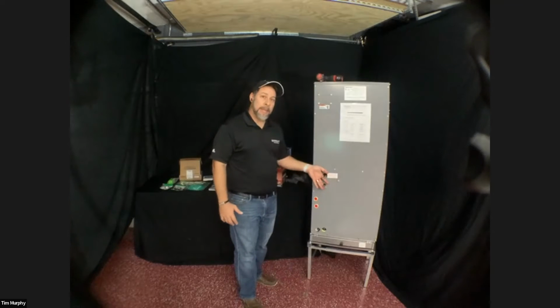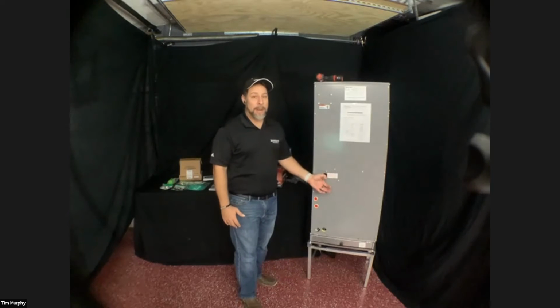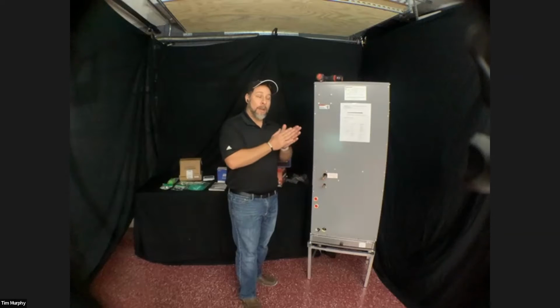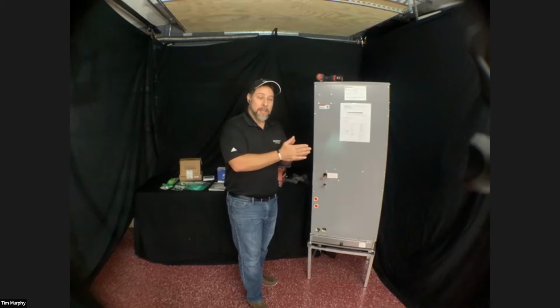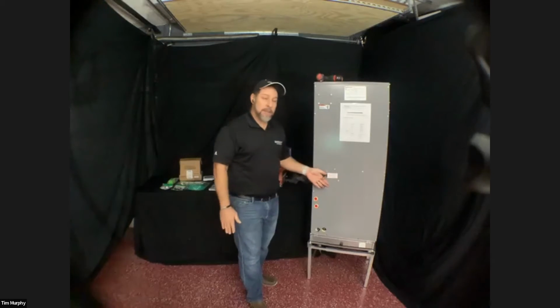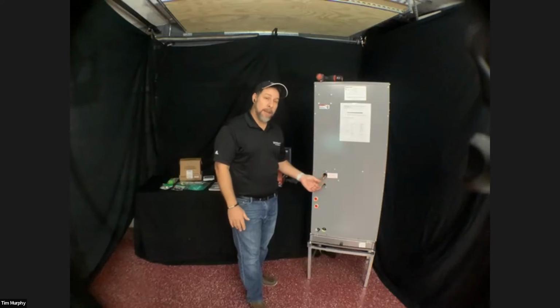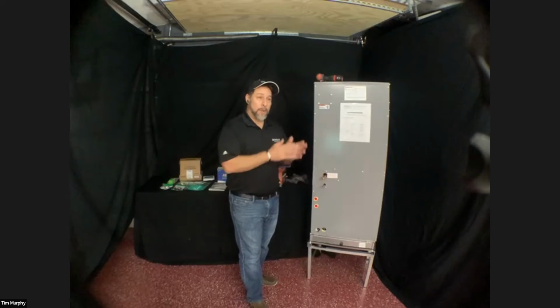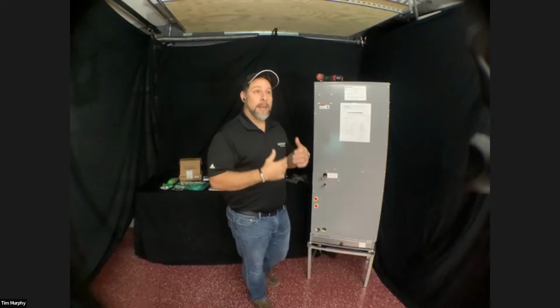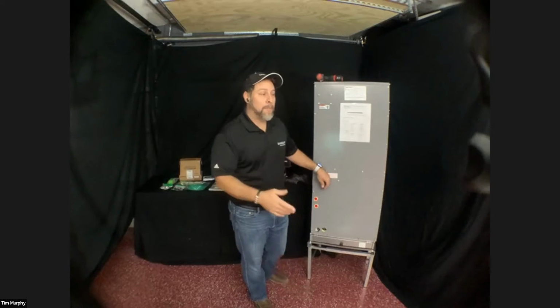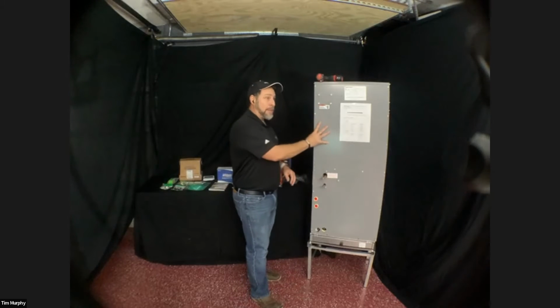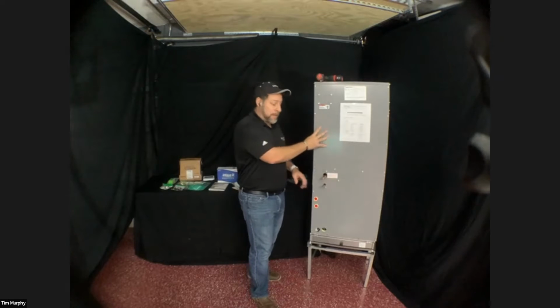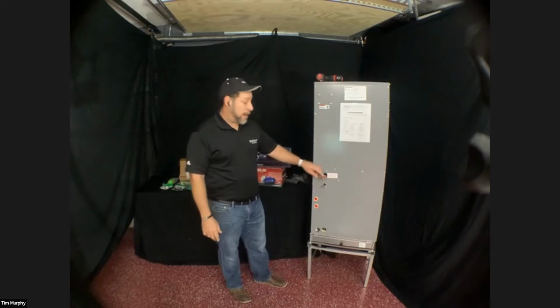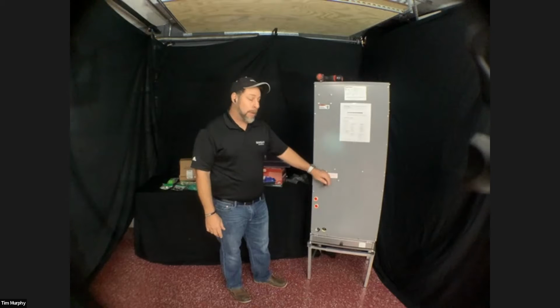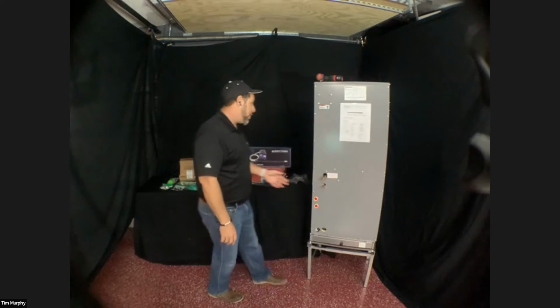The line set will need to be insulated separately because both lines are going to sweat, and you don't want to run them in the same insulation jacket either, because there's not going to be much temperature difference between the evap in and evap out. So you're going to want to make sure that they're insulated separately, but they're insulated well, and that they go all the way back to the condenser. If you notice, unlike a traditional mini split system, we do have sweat fittings, right? This is a sweat in coil. You can see it's capped off and it's sealed from the factory.